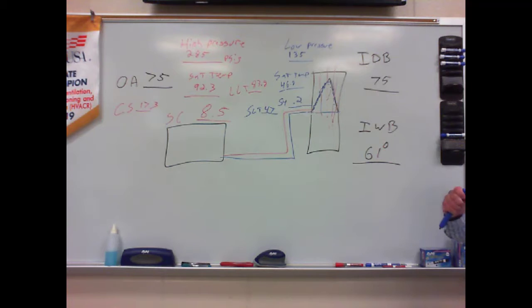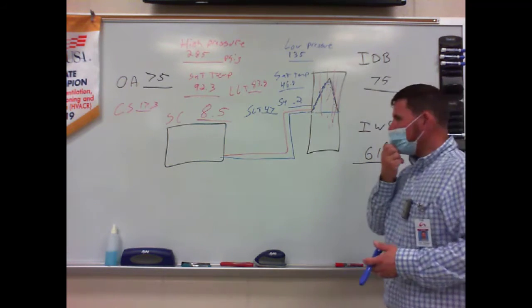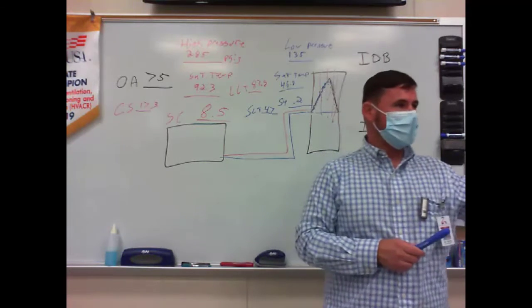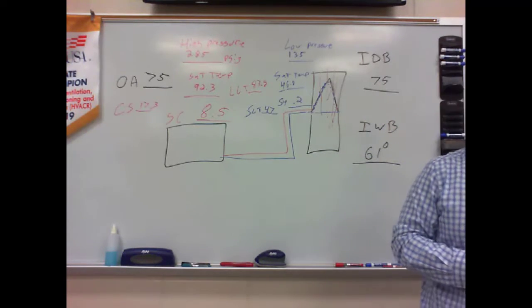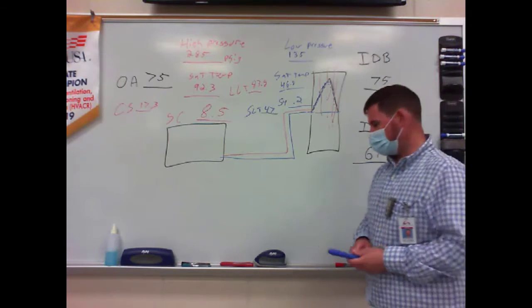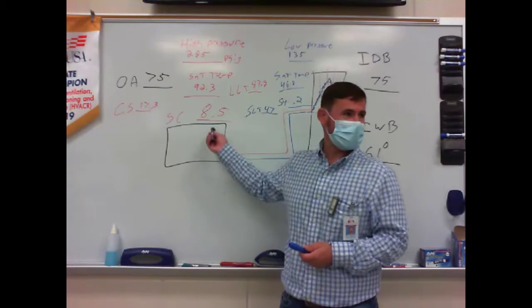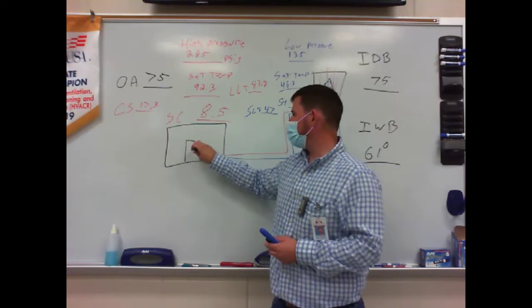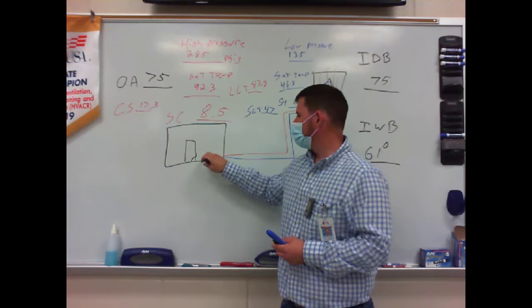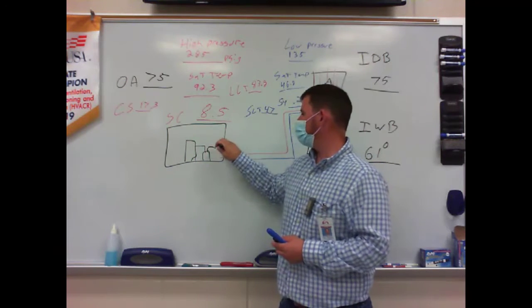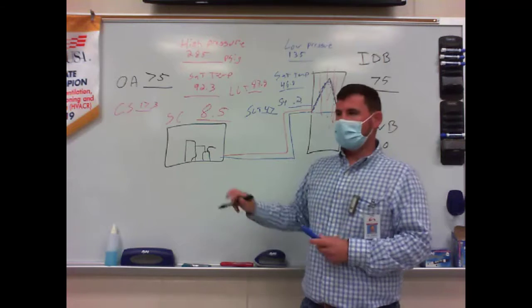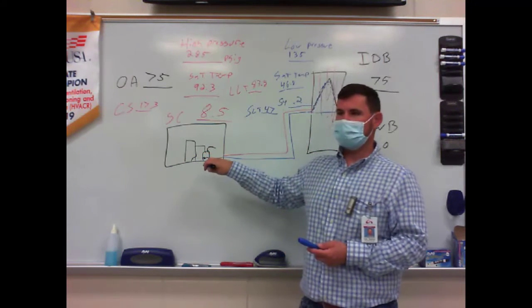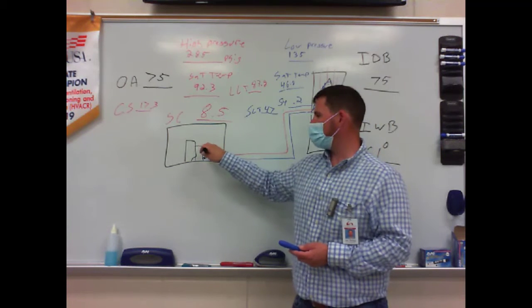All right, he asked how there's not liquid getting into that compressor. I don't know that there's not. There could be, but because it's a heat pump, we have an added component inside of there. Do you remember what it is? An accumulator, that's right. We go through our reversing valve first, right? And between our reversing valve and our compressor is that little accumulator. So if we do happen to have some liquid coming back, hopefully it will accumulate in here and all will be pumping back as vapor.